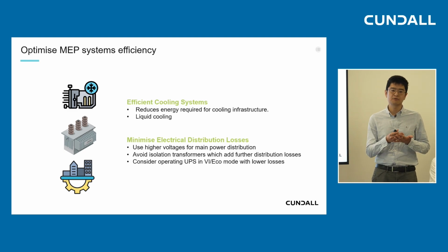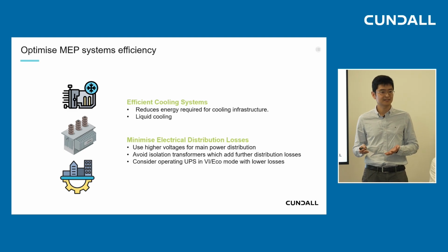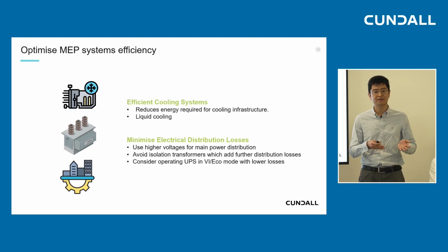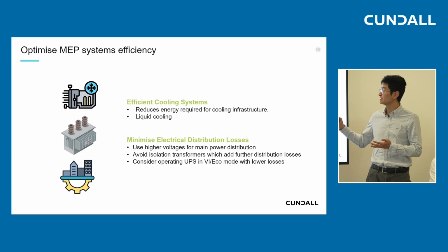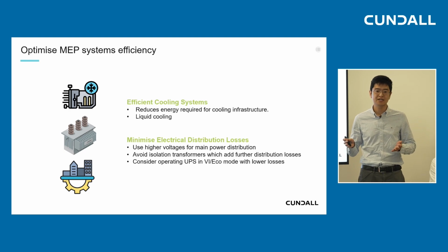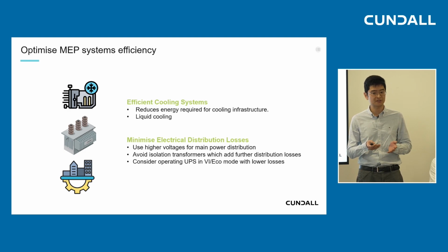On our recent projects, we have seen clients start to adopt liquid cooling in their data centers, which creates a lot of design challenges but also opportunities to further improve system efficiency, because the technical water loop for liquid cooling can operate at a much higher temperature compared to the traditional chilled water system.